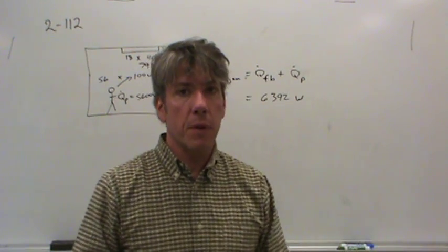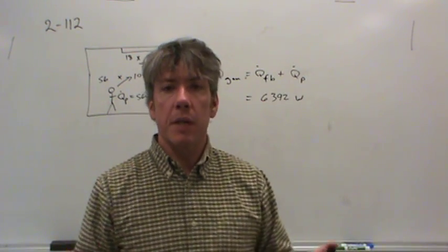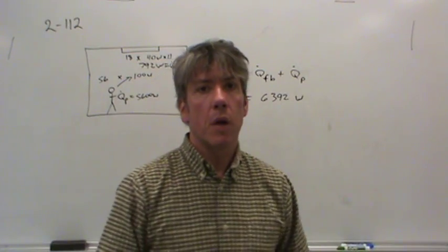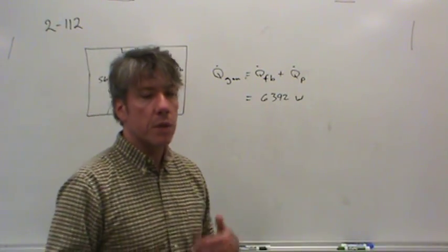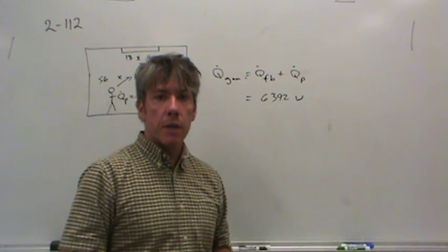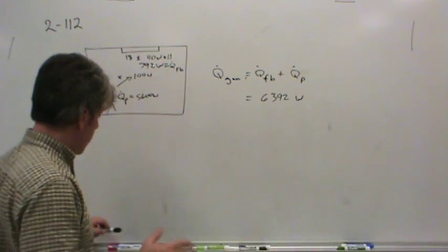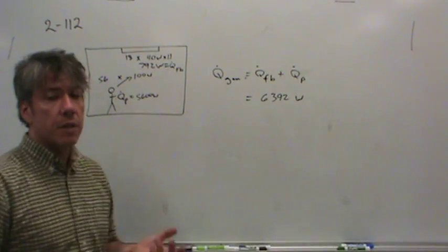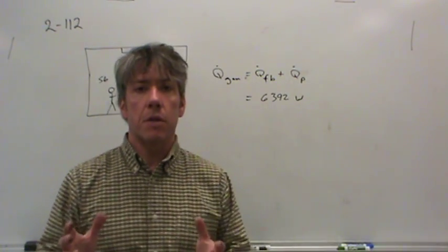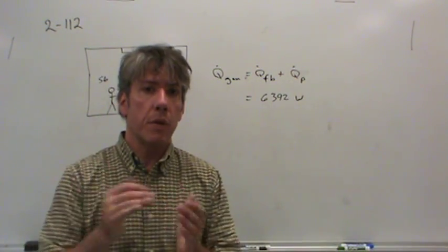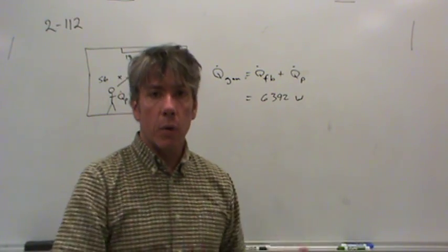Where would the humidity come from since there are no people there? Well, it could be many places, but mainly just diffusion from the outdoors would be one place. And so the air conditioner simply wouldn't run as long because there are no people in the room. There's no heat load. But then, see, so it's a trade-off, and you might actually choose to have the air conditioner have multiple stages so that it can actually run longer at a lower capacity.